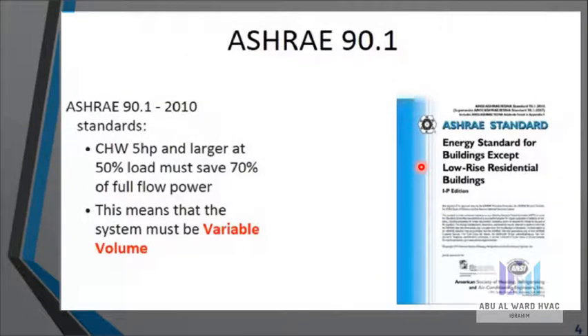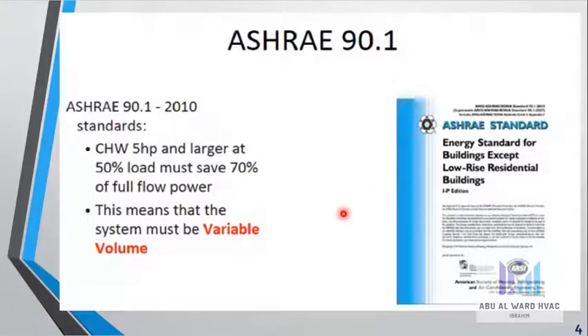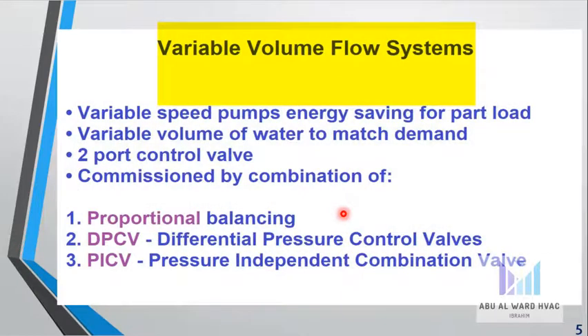According to ASHRAE 90.1, chilled water systems 5 horsepower and larger at 50% load must save 70% of full flow power. Variable volume flow systems use variable speed pumps for energy saving at part load.